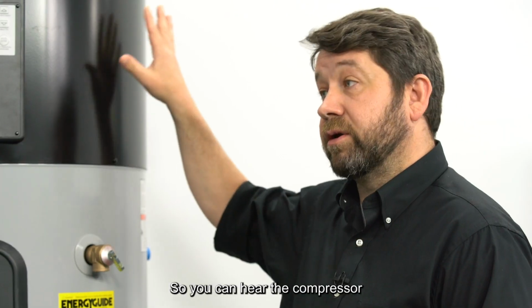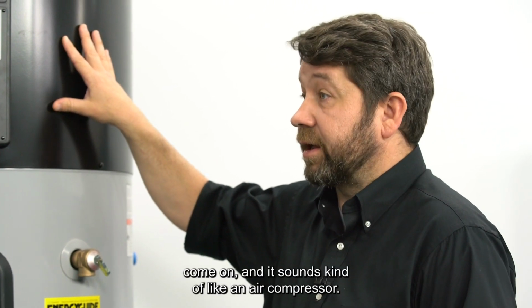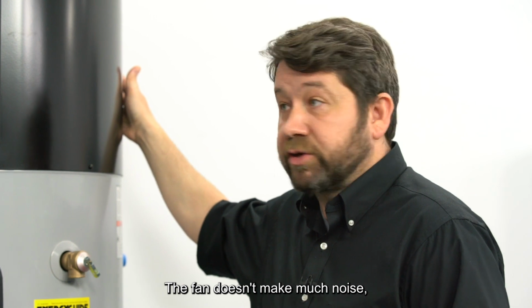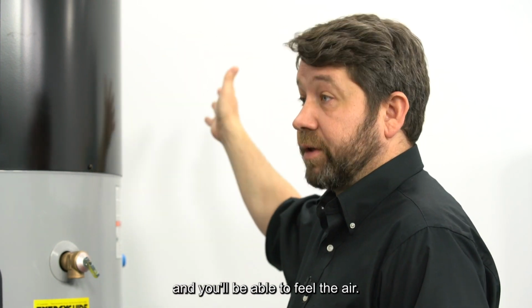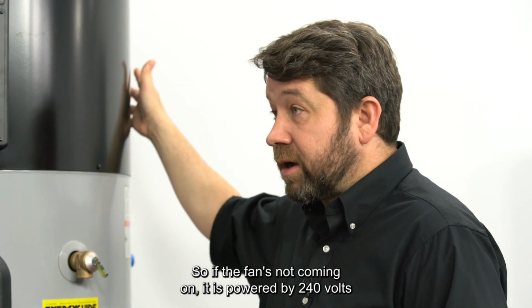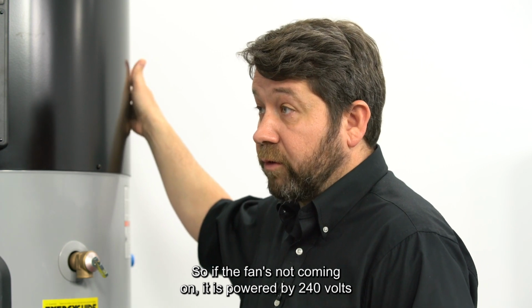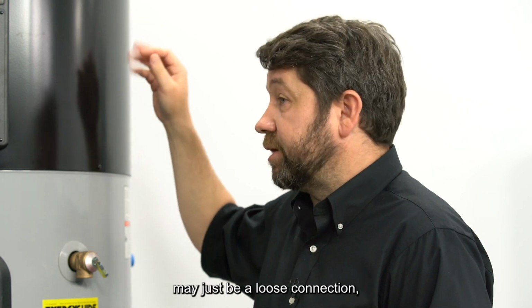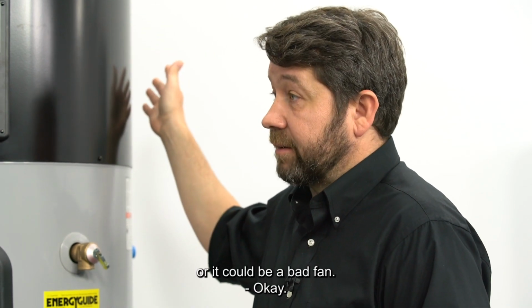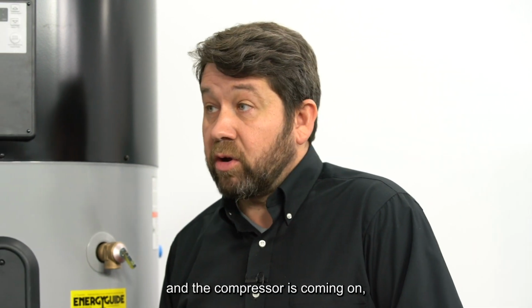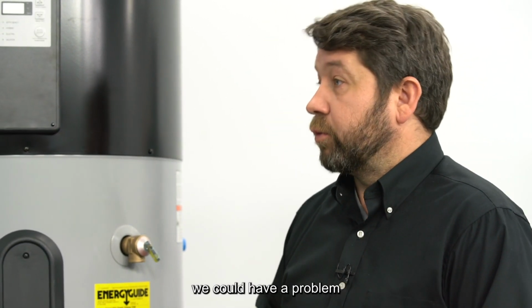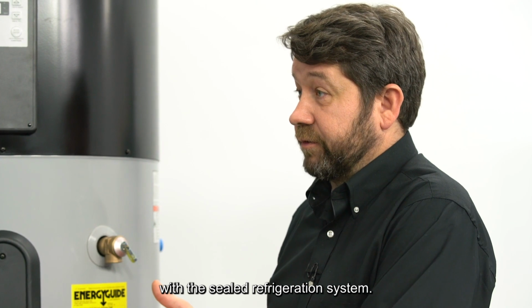Right. So you can hear the compressor come on, and it sounds kind of like an air compressor. The fan doesn't make much noise, but you'll be able to see it and you'll be able to feel the air. So if the fan's not coming on, it is powered by 240 volts that comes off the control board. It may just be a loose connection, or it could be a bad fan. Okay. But once we know the fan is coming on and the compressor is coming on, we could have a problem with the sealed refrigeration system.